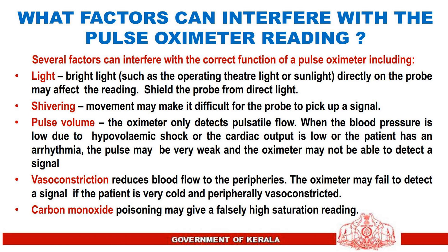Several factors can interfere with the correct function of a pulse oximeter. Bright light such as operating theater lights or sunlight directly on the probe may affect the reading — shield the probe from direct light. Shivering or movement may make it difficult for the probe to pick up a signal. Pulse volume: the oximeter only detects pulsatile flow — when blood pressure is low due to hypovolemic shock, low cardiac output, or arrhythmia, the pulse may be too weak to detect. Vasoconstriction reduces blood flow to the peripheries, and the oximeter may fail to detect a signal if the patient is very cold. Carbon monoxide poisoning may give a falsely high saturation reading.